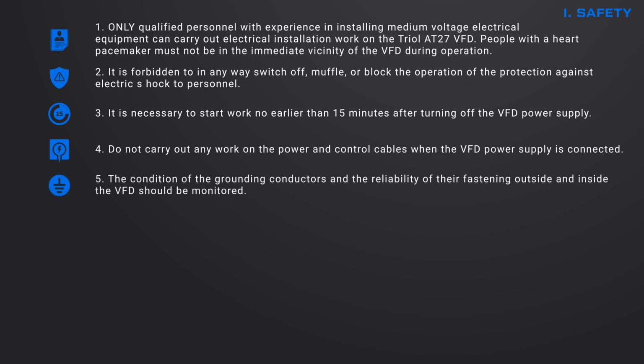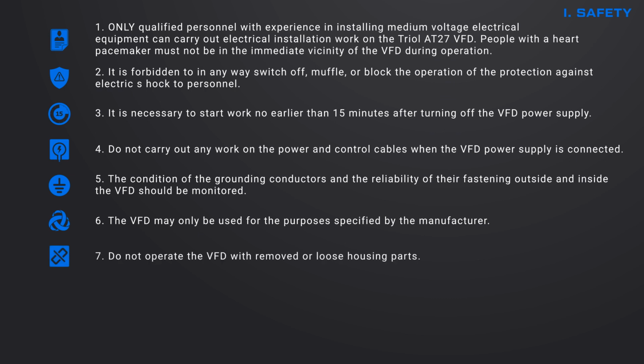To ensure the safety of personnel, as well as to reduce the level of electromagnetic radiation and improve noise immunity, the condition of the grounding conductors and the reliability of their fastening outside and inside the VFD should be monitored. The VFD may only be used for the purposes specified by the manufacturer. Unauthorized modifications and use of spare parts and accessories not manufactured or recommended by the manufacturer of the VFD may cause fire, electric shock, or injury, and may void the manufacturer's warranty.